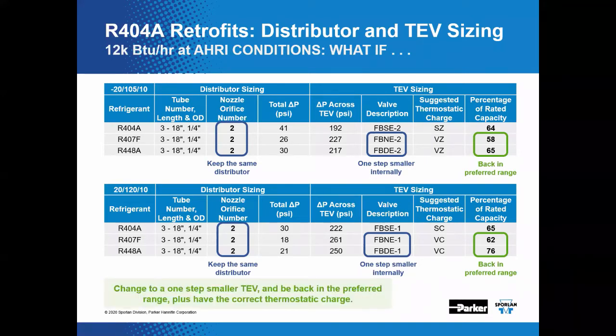The point here is not that we need to change out every R404A TEV in a retrofit when we're doing a retrofit to 407F or 448A, but it's to be cautious and check the sizing of the valve. Even if the percent loading is marginal, changing to a lower force VZ or VC, that's the R22 low temp and R22 designated medium temp thermostatic charge element construction, could help regain needed superheat adjustment range, yielding better superheat control in the long run.